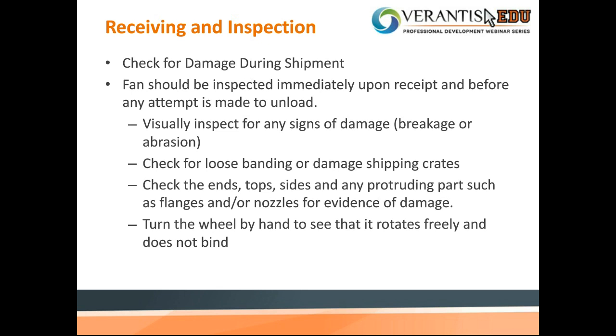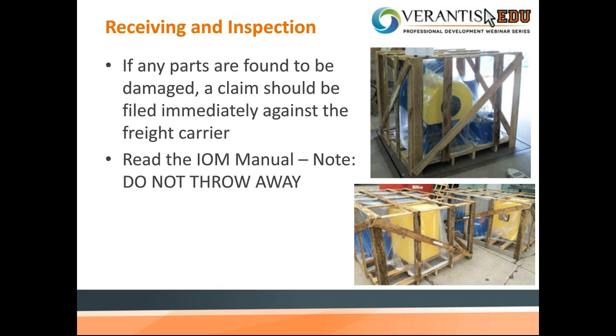But always, with every fan that we get, any fan that you get on site, read the IOM manual. Don't throw it away. It's always some good information. And if any parts are found to be damaged, a claim should be filed immediately against the freight carrier. That's because once the fan gets installed, there's not much you can do about it, and you want to make sure this thing is properly functioning by the time you get to that point.